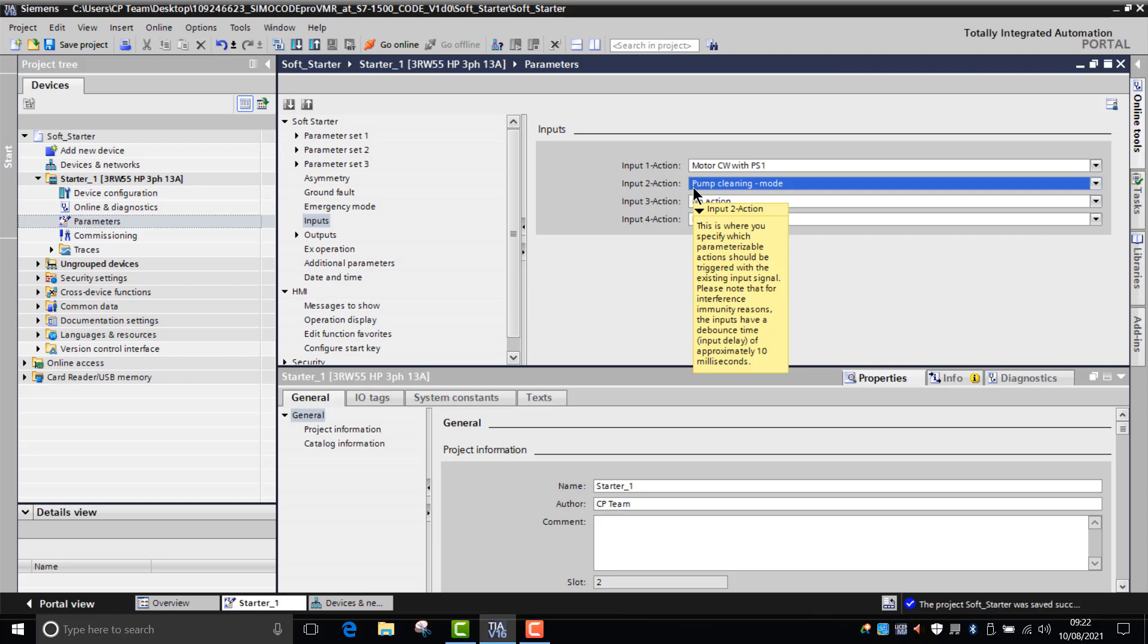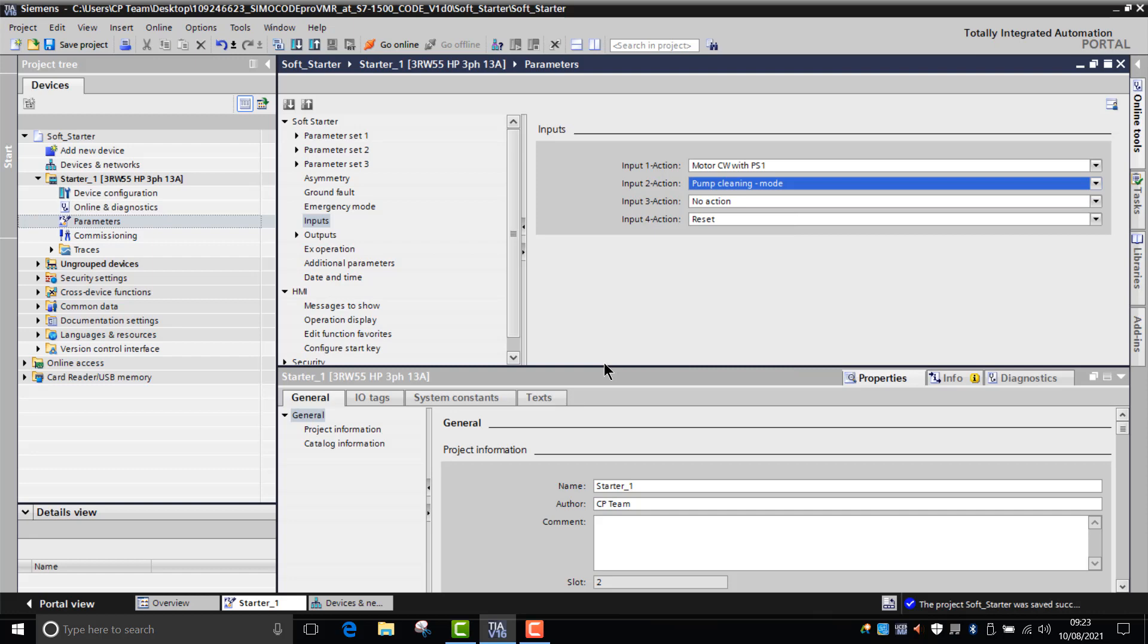Another way would be to go over the network. If you had the soft starter being controlled over an automation network via PROFINET, say, you could access one of the memory inputs called pump clean and you could trigger a pump clean that way. So that basically shows you how to parameterize the pump cleaning function.